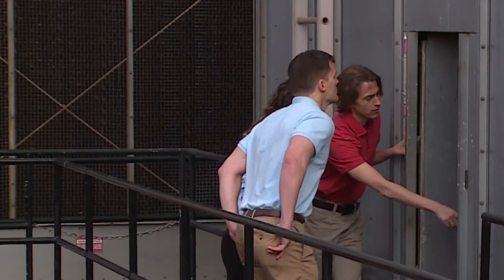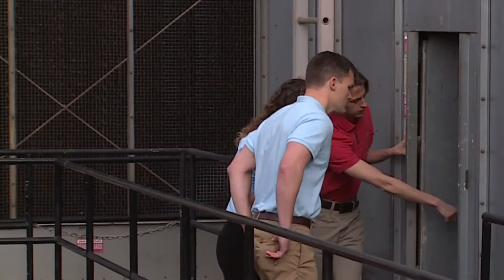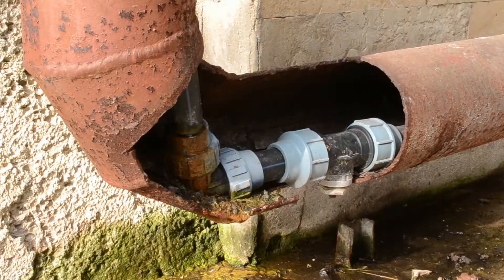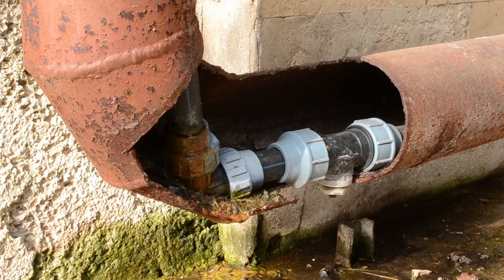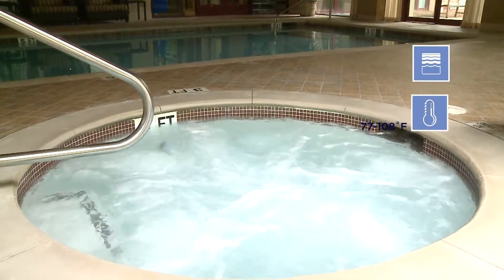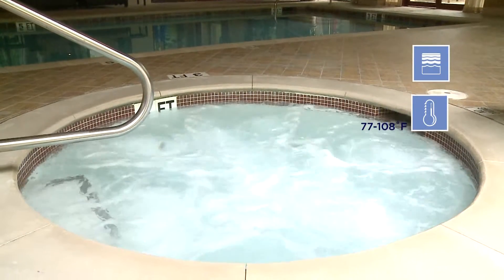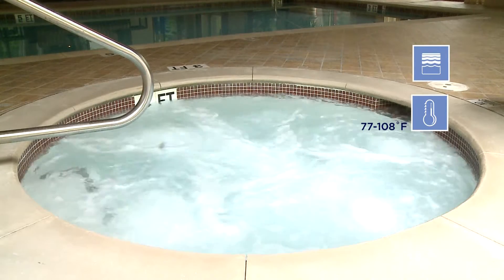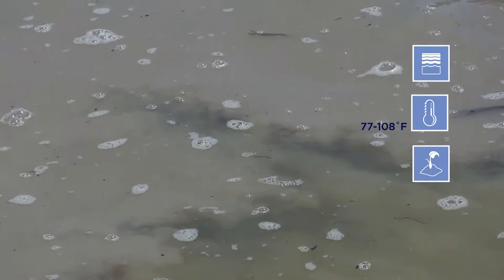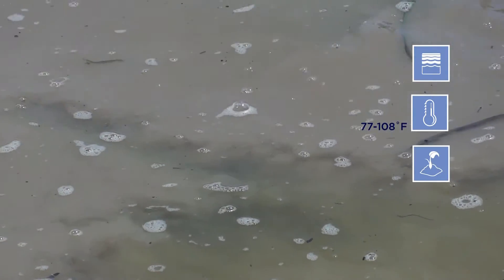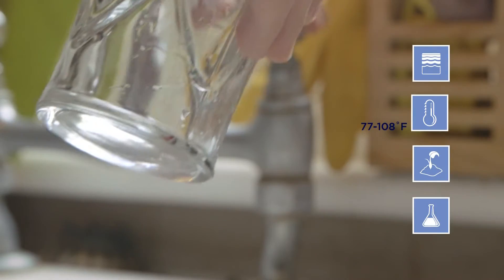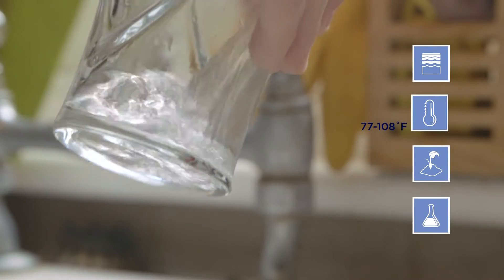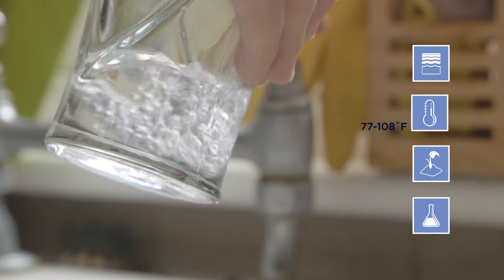When you perform an assessment, remember Legionella grows best in water that is stagnant, warm between 77 and 108 degrees Fahrenheit, with organic matter and lacking residual disinfectant like chlorine.